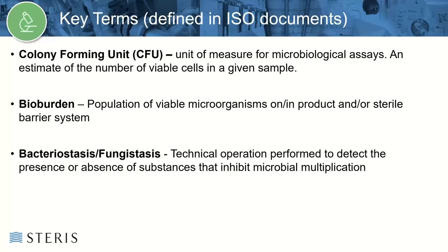Let's review some key terms that will come up throughout the webinar. Colony forming units are our microbiological unit of measure. In theory, during incubation, a single cell replicates on growth media to give rise to a visible colony. These colonies can be counted to give an estimate of the viable contamination on a sample. This estimated number of colony forming units on a device is then referred to as the device bioburden — the population of viable microorganisms on or in a product and or sterile barrier system. Bacteriostasis fungistasis is the test used to ensure that the sterility test method is not inhibited by the presence of the device, which could lead to a potentially false negative or no growth result.